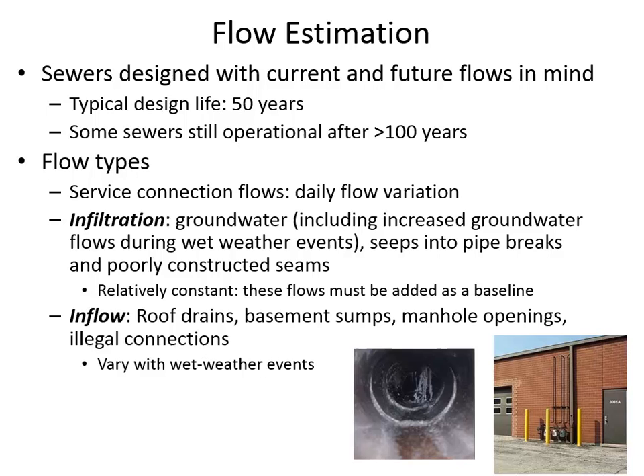You know you've got infiltration if the strength of the wastewater is relatively low — this is measured by BOD (biochemical oxygen demand), which you'll learn about next fall. A relatively weak sewage with low strength may indicate infiltration. Cities also do inspections using cameras on long fiber optic cables, or remote-controlled cars driven through the sewer. They visually inspect pipes every couple of years to get through the entire network.